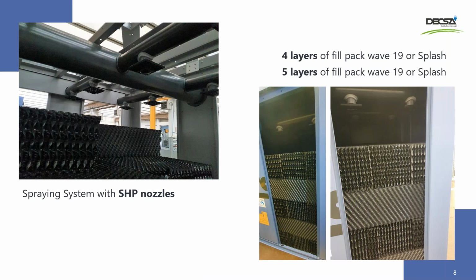A very important part of the SQA design is the spraying system and the number of fill pack layers that we have on the SQA cooling tower. The spraying system is made with SHP nozzles that are specifically designed for water with suspended solids. SHP nozzles have a higher water flow compared with standard nozzles. So, thanks to this specific characteristic, there is a smaller number of nozzles and a shorter maintenance time has to be considered, allowing a cost reduction.